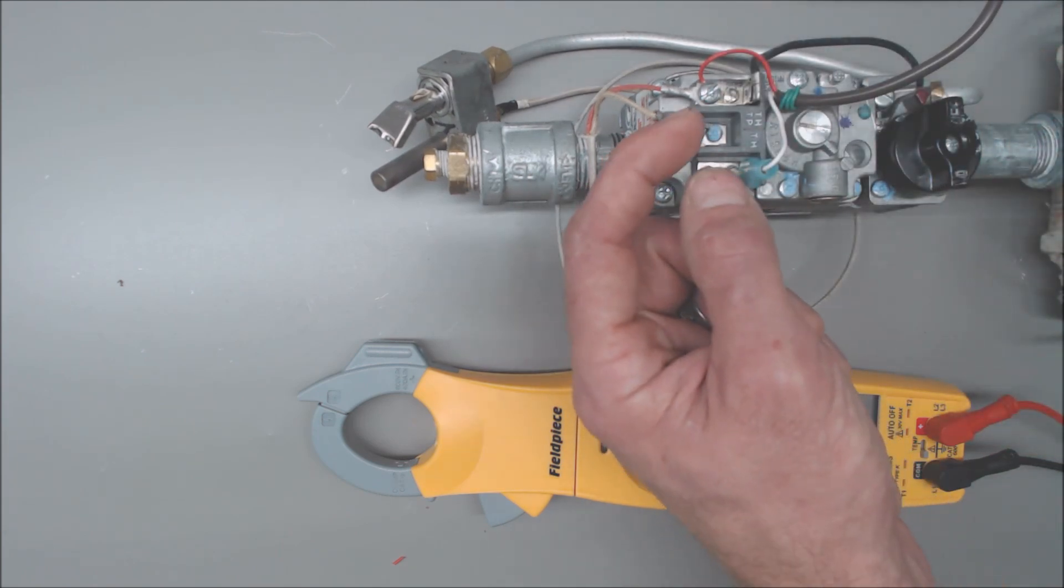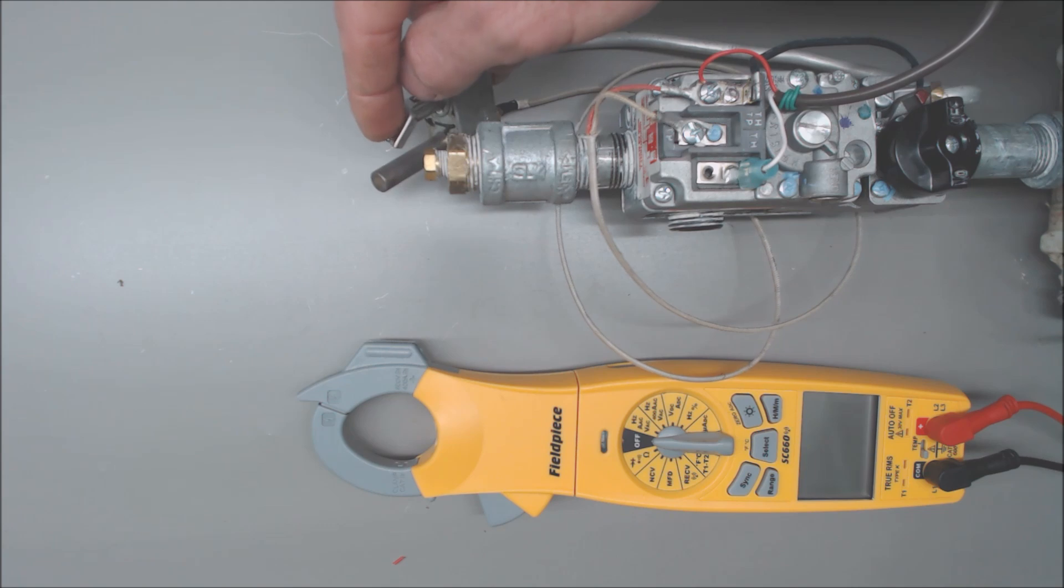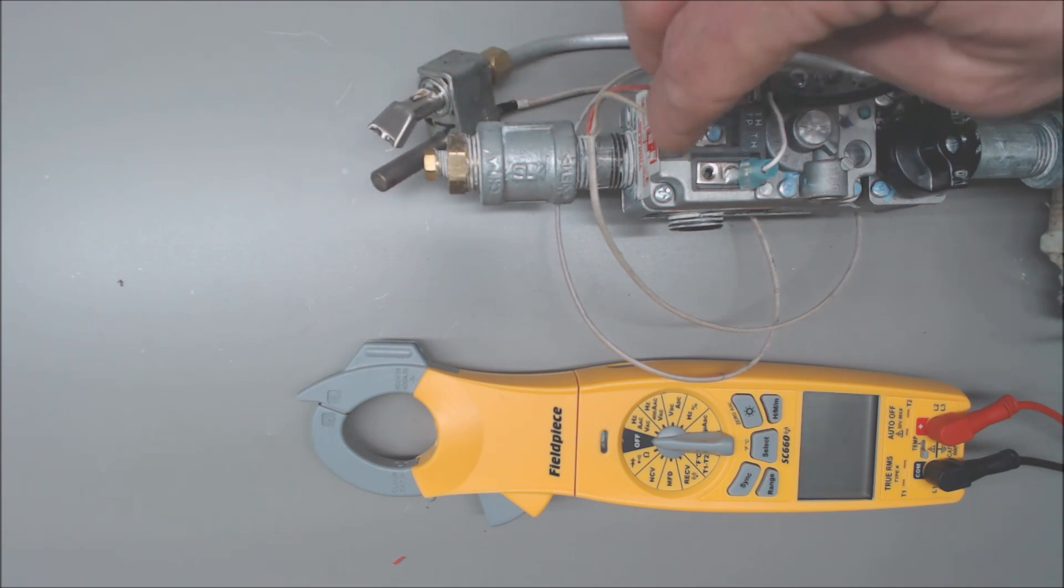These two are your main valve and these two are your pilot valve. You see that this flame is actually going to hit this thermopile and it's going to send millivolts DC to your pilot valve.